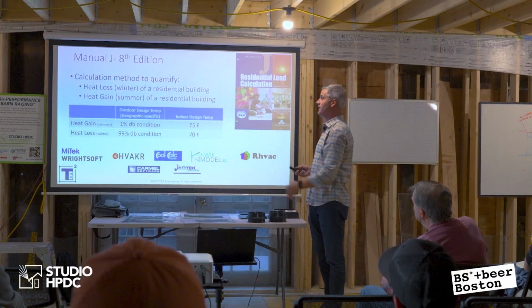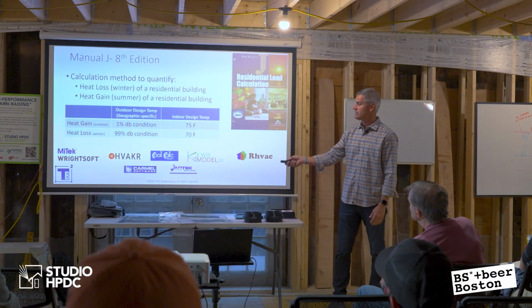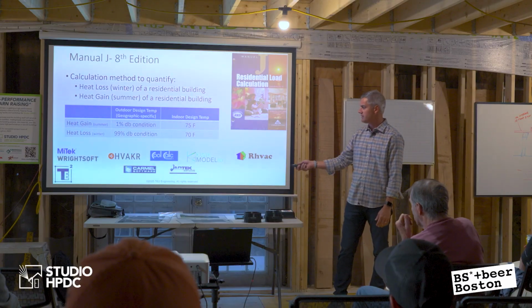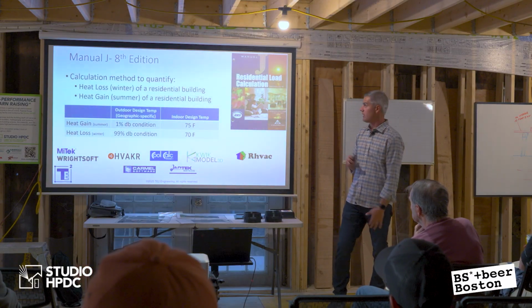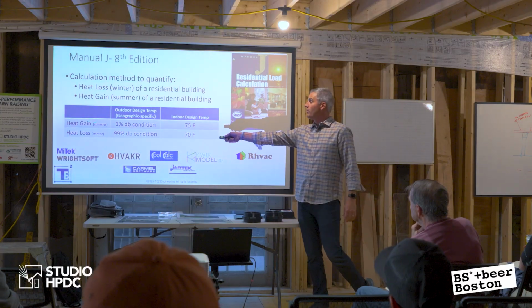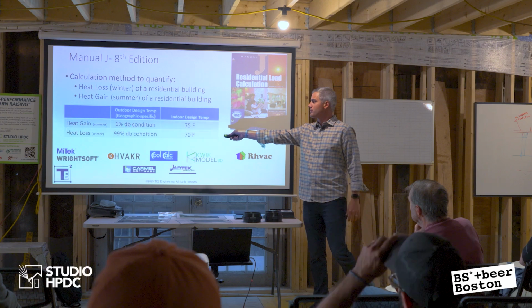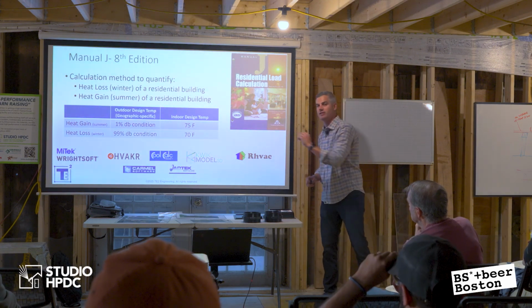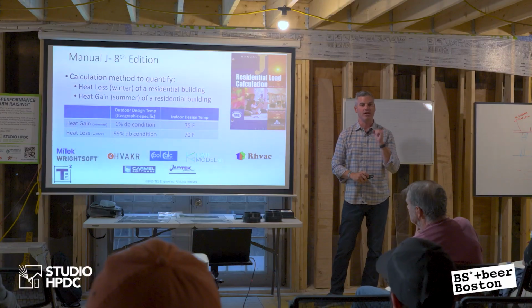So Manual J is in its 8th edition. They're actually working on the 9th edition right now. Here are some of the software we use: Wrightsoft, HVAKR, Cool Calc, Quick Model, Rhvac from Elite, Carmel, AdTech. All different versions of it, all have different pros and cons. But at the end of the day, what we're doing is a heat gain calculation. So we're picking, and we'll talk about this, a 1% design condition and 75 inside. We do a summer snapshot and a winter snapshot of the building to figure out how much energy it needs for heating and cooling.